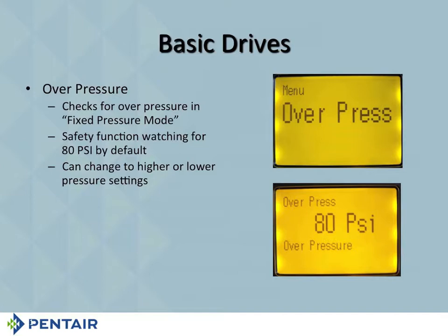Now, the reason I said 97 is because, remember, that's the highest pressure that I can have with this drive. I can't go over that. And the reason I can't go over it is because of the fact that you've got 100 pounds max on your pressure transducer. So if you hit 3 PSI, in order to hit that 3 PSI, 97 has to be your maximum pressure you can set it for. And once the drive goes into that, it says, okay, do I need to go to sleep? No, it won't overpressure. It can't overpressure. So 97 is the max unless you put on a different transducer. Then you got to change that.